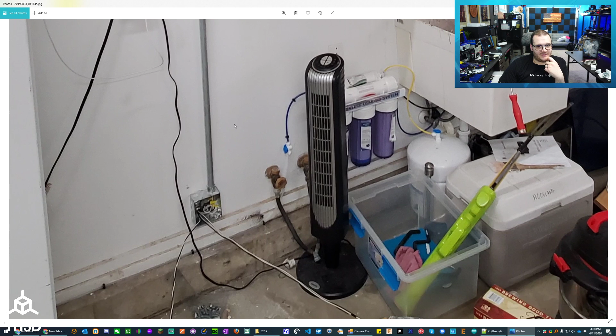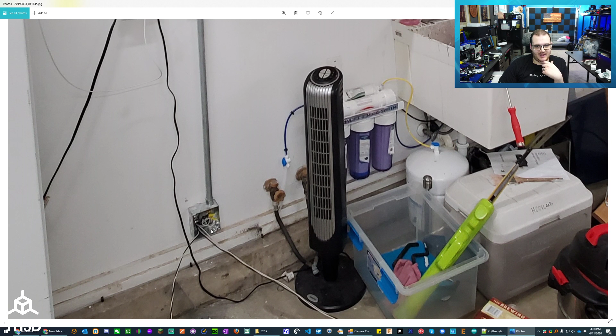Here's how I did this: there's a 3/4 inch conduit going into the basement, terminated to this box. All the grounds are bonded together onto an eyelet and then grounded to the conduit. There are 4 circuits total in here — three 110s and one 220, all 20 amp, 12 gauge. I used Romex through the basement from the sub panel to this box, then 12 gauge stranded wire through the conduit. These four outlets are on their own circuit, and this is just a junction box.